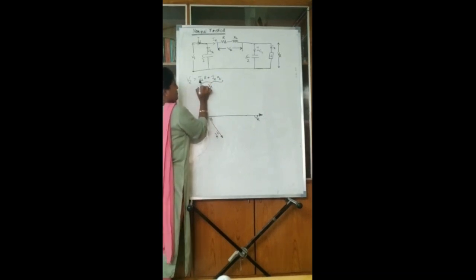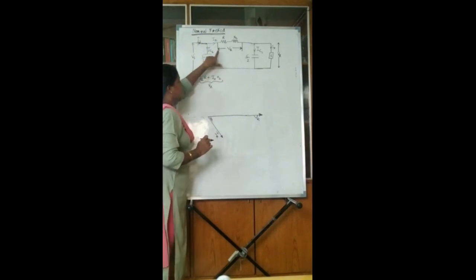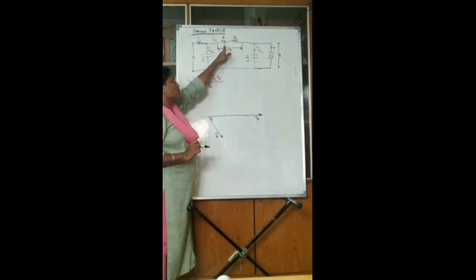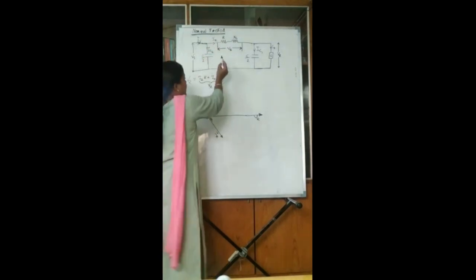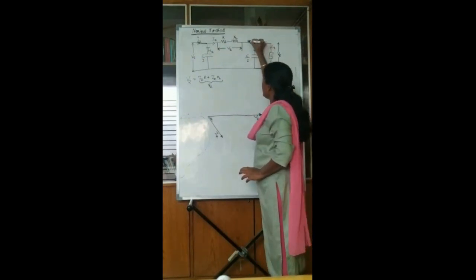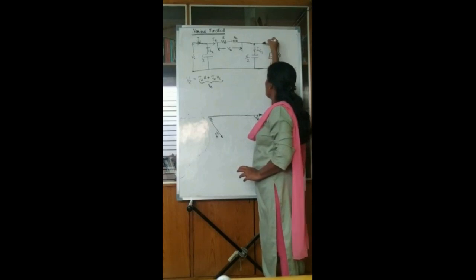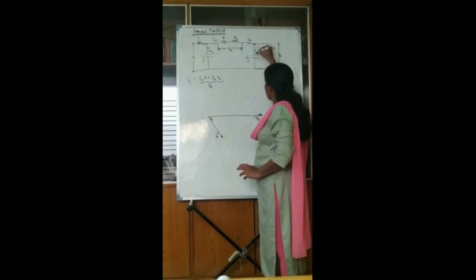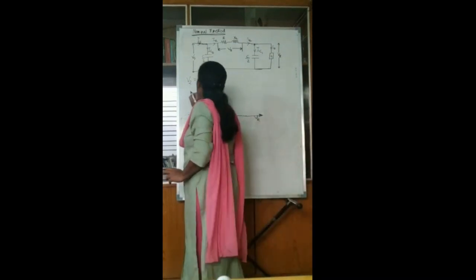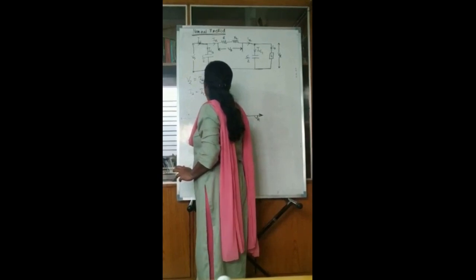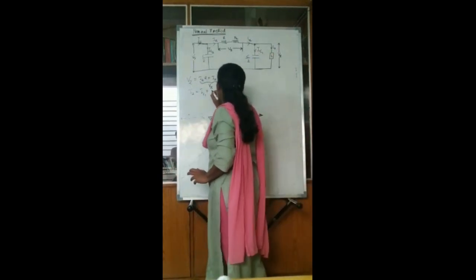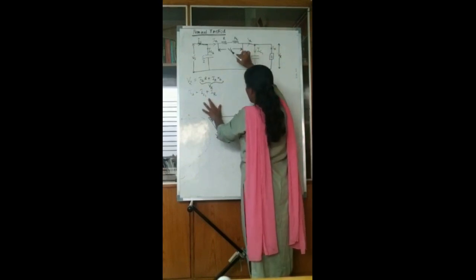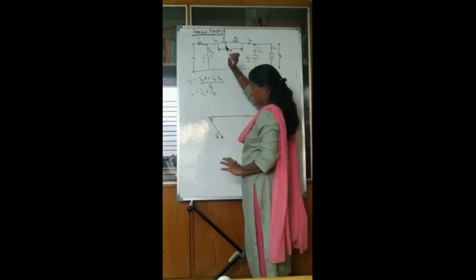To find Vz I first need to find Iz, and to find Iz I need to find the currents at the receiving-end node. At that node, Is1 and Ir are the two branch currents, and the vectorial addition of Is1 plus Ir will give us Iz. So I must find Is1 first, then find Vz, and then add it to Vr to get Vs.